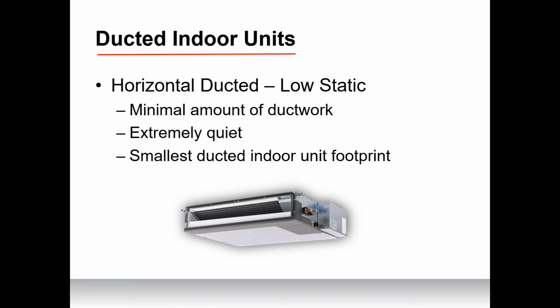So there's 3 basic types of ducted indoor units. First, here we have the horizontal ducted indoor unit. This is a low static air handler, meaning it's not built to move a lot of air. It can if it's designed correctly. It just has very low external static pressure and lower CFM. So it's really designed for a limited amount of ductwork. You can put more ductwork on here. You just have to make sure you're doing a really efficient duct design on it.